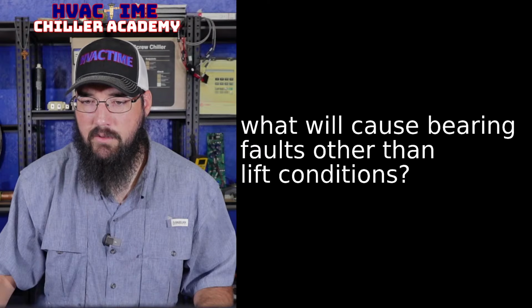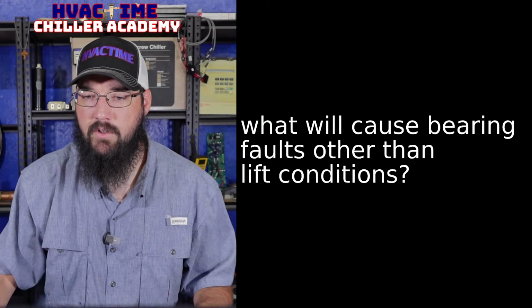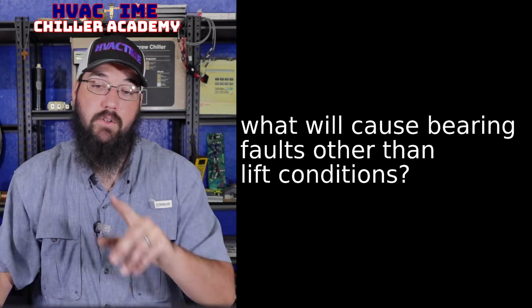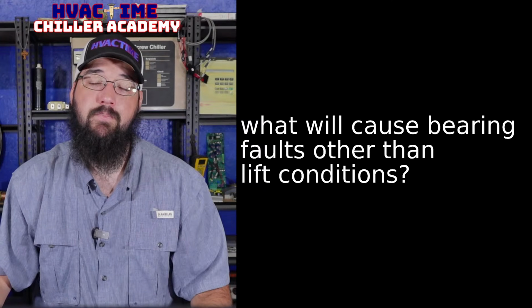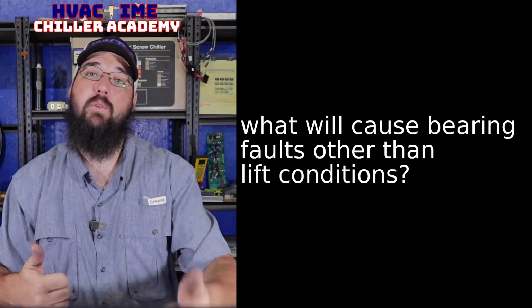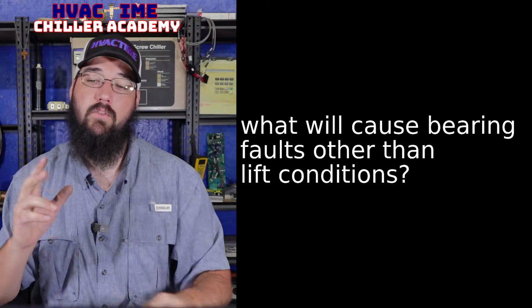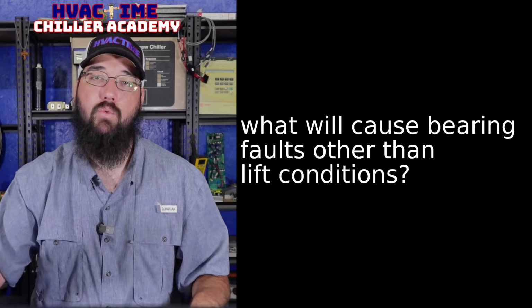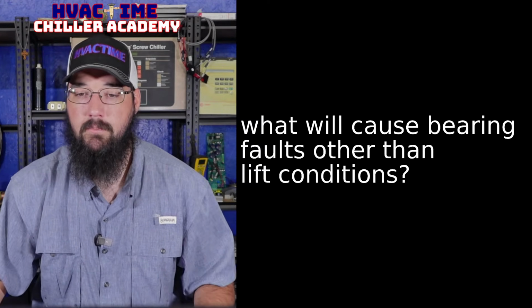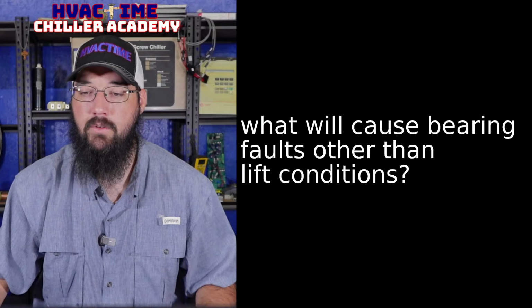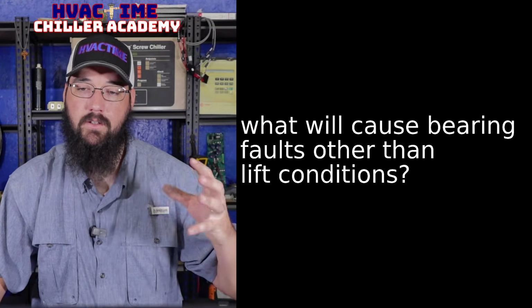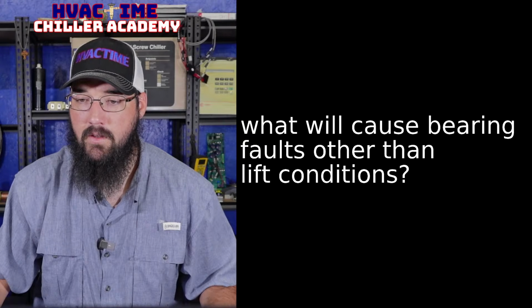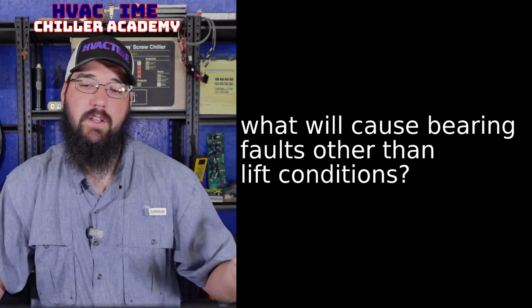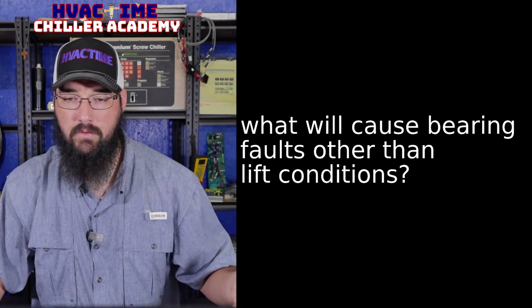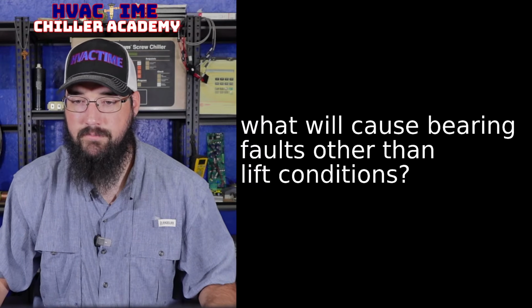See, liquid in suction will cause bearing faults. Yeah, that's a good point. If you start running a wet suction, whether it be through the economizer or through the suction line itself, if you start having too wet of a suction, Tom is right there, that actually is one that will cause a bearing fault as well. Another way to say that in centrifugal terms is carryover. We start having too much carryover.